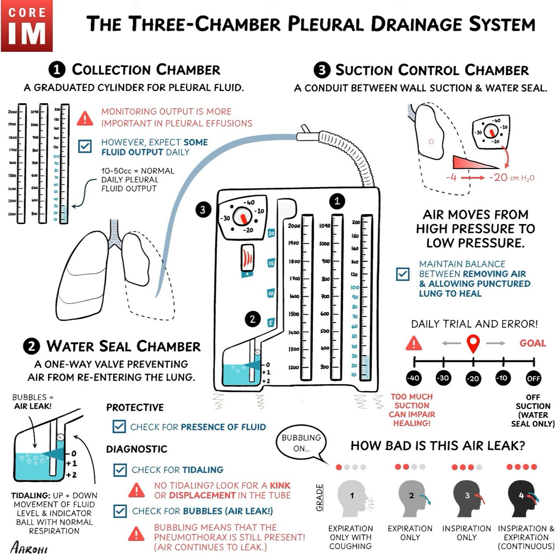And the last one is a suction chamber, which is usually on the left-hand side. And depending on the system you're using, it might be a circle knob. So suction is added to help draw out more air from the chest. And this chamber looks like a dial to show what degree of suction is being applied. And it also is needed because once the specific pressure is set, the valve pops off and closes to ensure that the amount of pressure is stable to prevent patient injury.